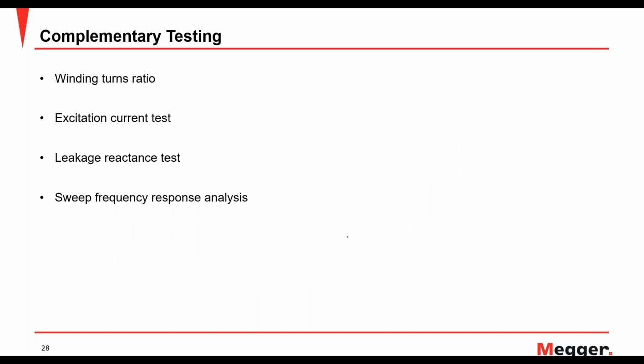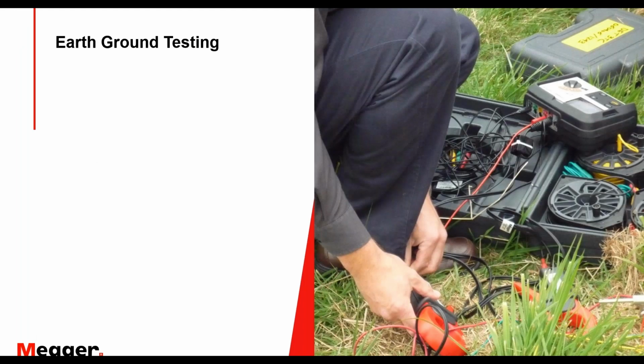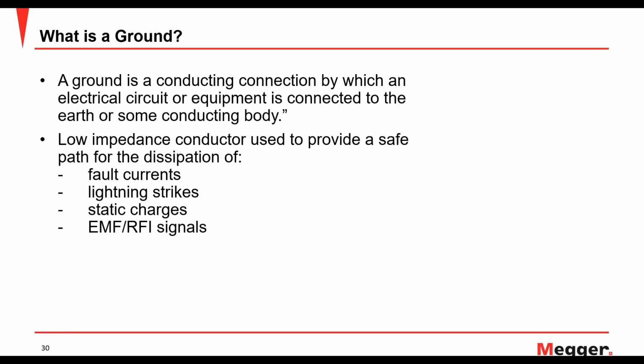And what are the other complementary tests that you can do on the transformer? You can do turns ratio, excitation current, leakage reactance, sweep frequency response, that is SFRA, or power factor. Now, let's move on to the earth ground testing, a little bit about the transformer itself. What is a ground? It basically provides a low resistance path for anything to dissipate or discharge, typically fault currents, lightning strikes, any static charges in the equipment, or any residual EMF.